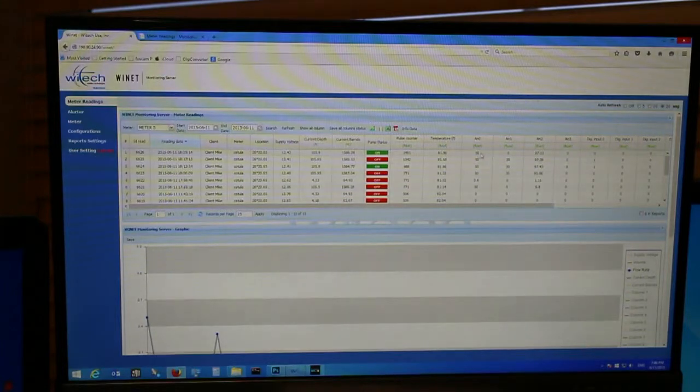The analog input 0 is used if you hook this up here and you measure this, it's going to show you from 0 to 50 in this case, because I have set up in the unit that the 0 and span is 0 and 50. 4 and 20 milliamps, it's 0 and 50, whatever, 50 feet, 50 psi, whatever.